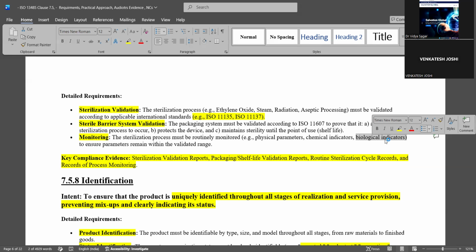There will be chemical indicators where there is a change of color after sterilization, from blue to green or red to yellow, something like that. But chemical indicators are not reliable. You should not depend on chemical indicators. It's always better to depend on your sterilization validation report, your sterility test reports, and your biological indicators. Chemical indicators sometimes show wrong results. When they do, you'll think the product is sterile and you will sell products which are unsterile. That will cause problems to the safety of the patient who uses it.